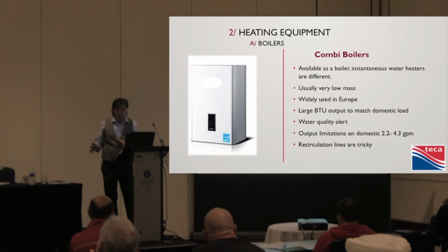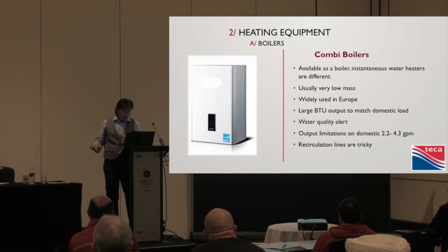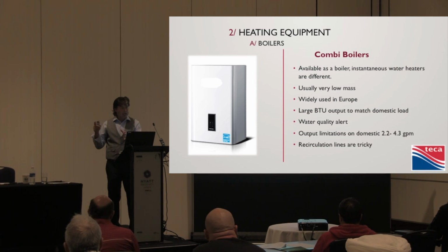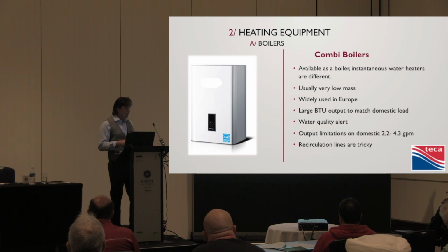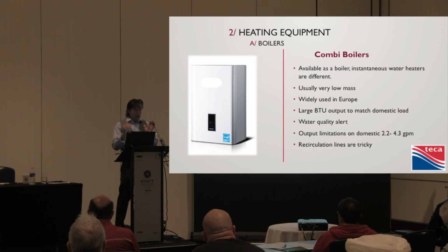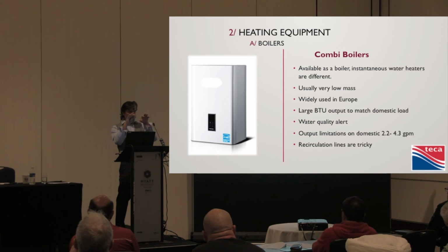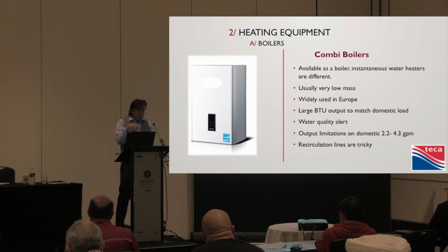In a tank style, well, what's the big deal? You just circulate to the actual tank, and you're circulating the tank. But when you're heating water instantaneously, it's flow sensitive. At 0.4 GPM, the burner comes on, comes alive, and it modulates down, and it wants to heat water. Because you might be cracking open a kitchen faucet for 2 seconds, or a bathroom, or their own tub filler. Who knows? It has to modulate the burner.